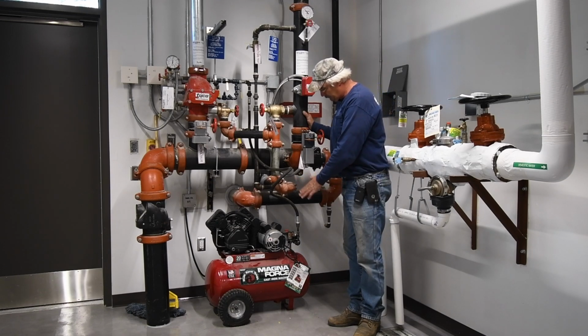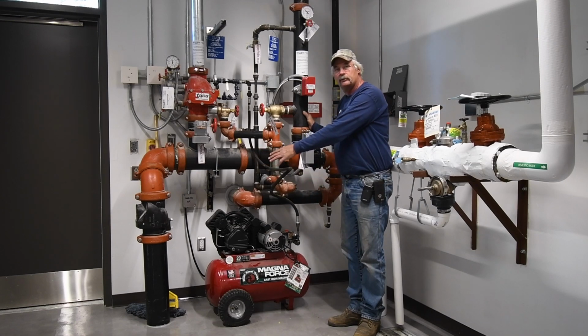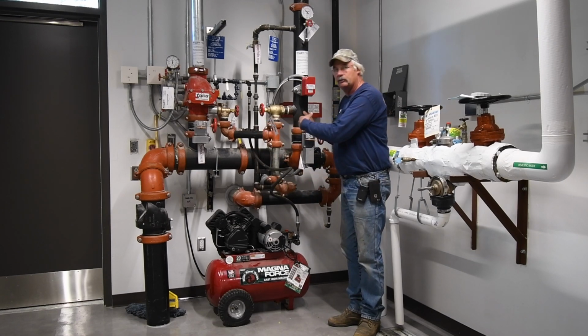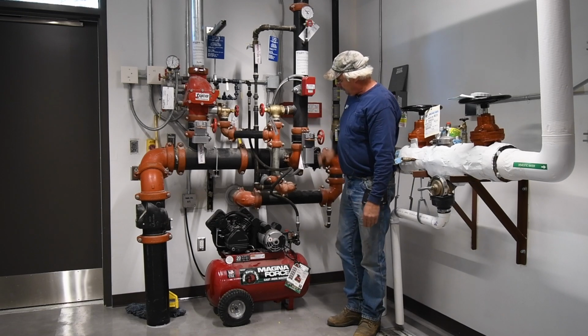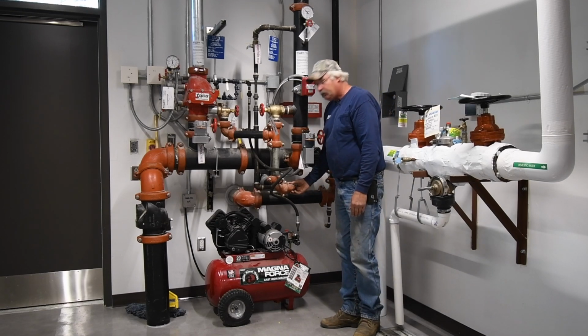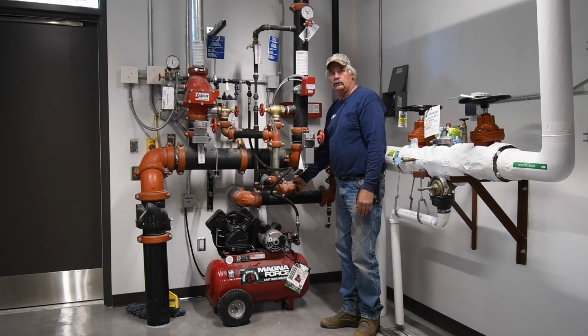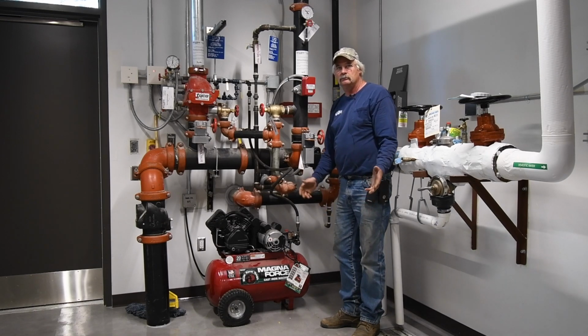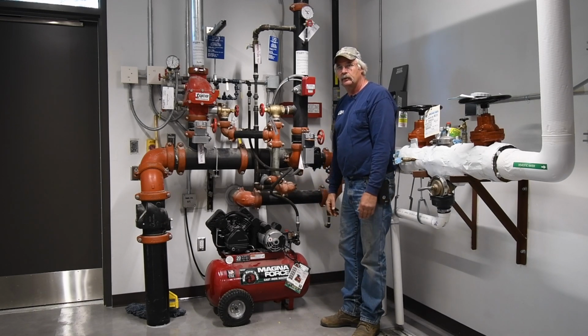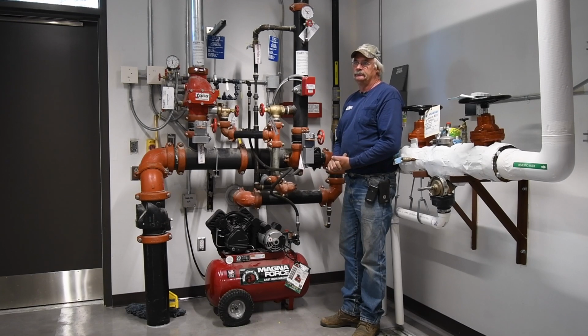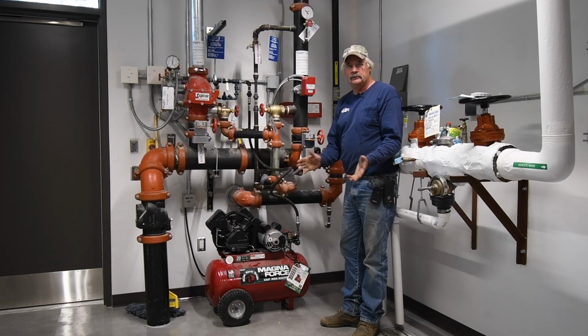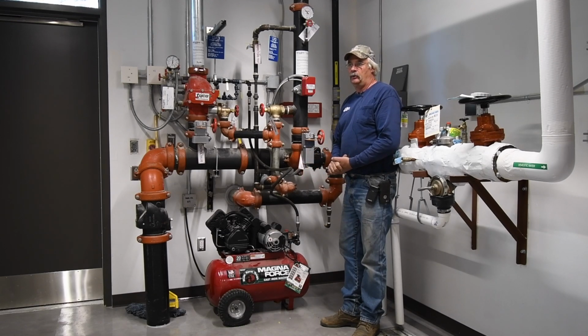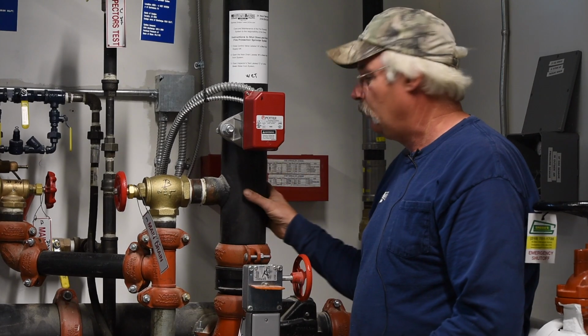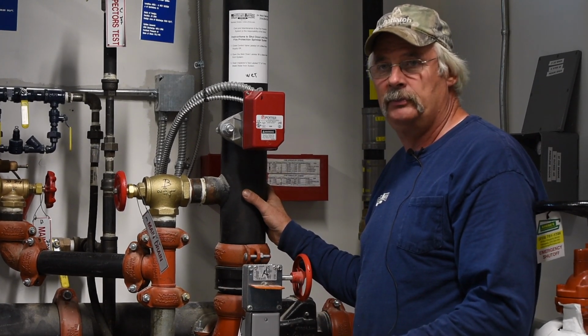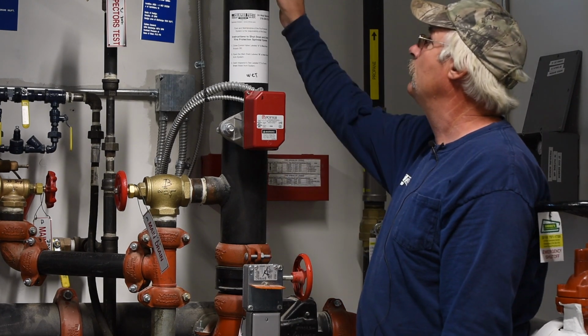You've got an air compressor, a riser coming in from the underground, you have a dry system, you have a wet system. One thing to remember is all the drains are piped to the outside of the building, so you don't have to worry about water or anything like that. In case of heat loss in a facility, one of the concerns they have is freezing of the pipe on a wet system. The care and maintenance is by the owner.